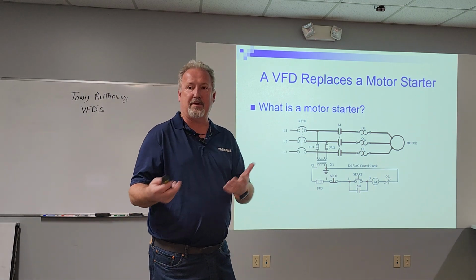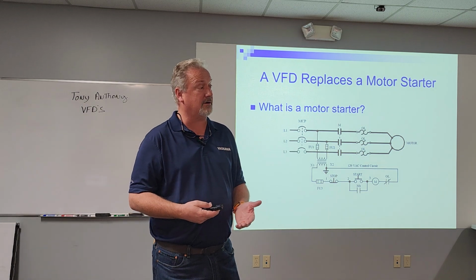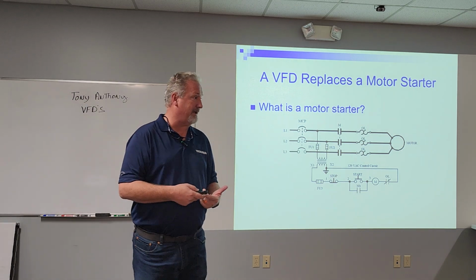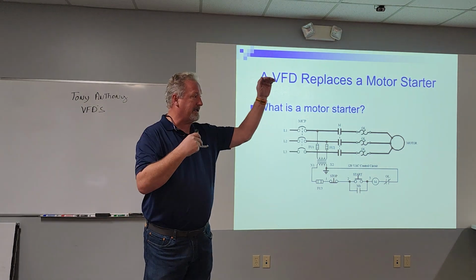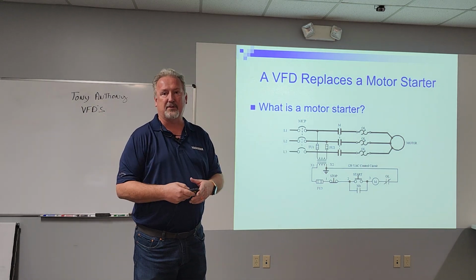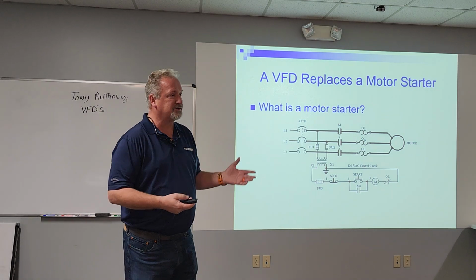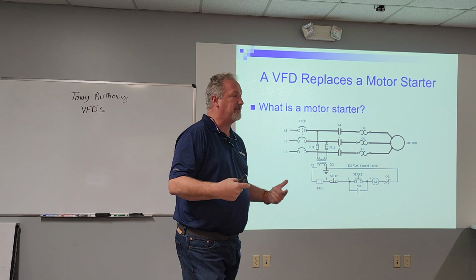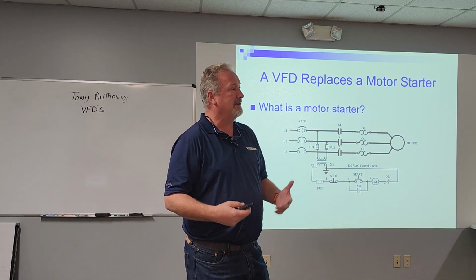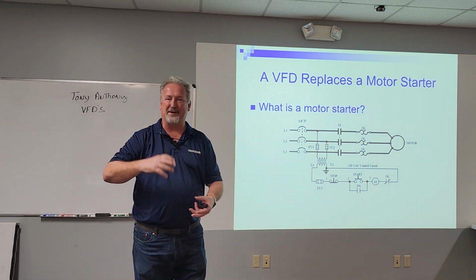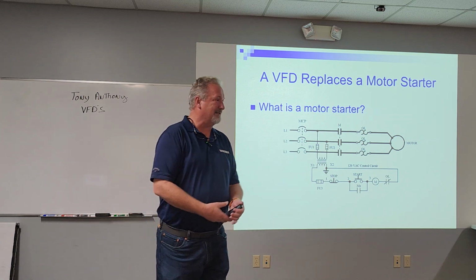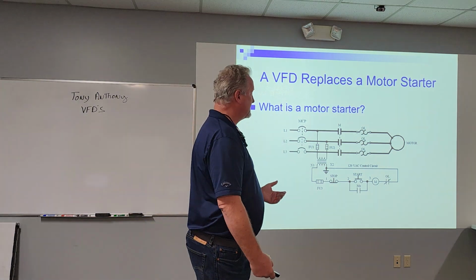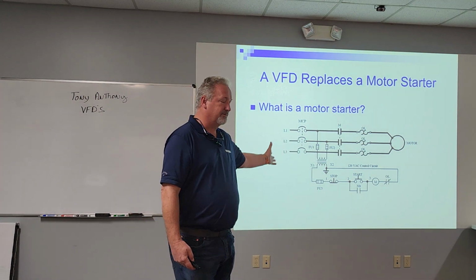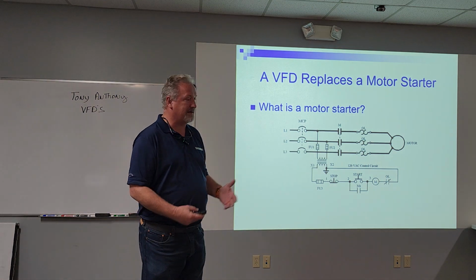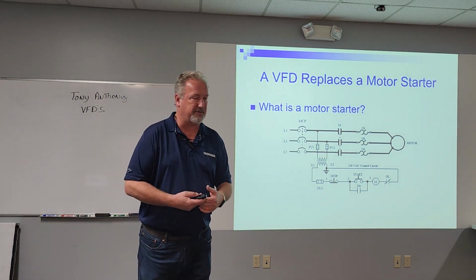And if you're a building or a company that gets charged for peak energy demands, so like whatever your peak is, that's like your 15 or 30 minute interval, that's a big hit. Also, if you're on a fan with belts or a pump with belts, you ever start a motor, you see those belts jumping, hopping. A lot of wear and tear on the belts. And with these across-the-line starters, you'll find you end up having to replace the belts often.